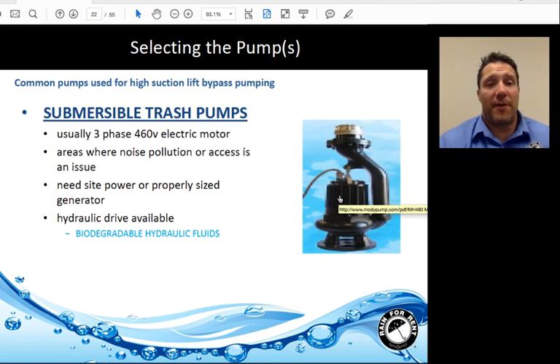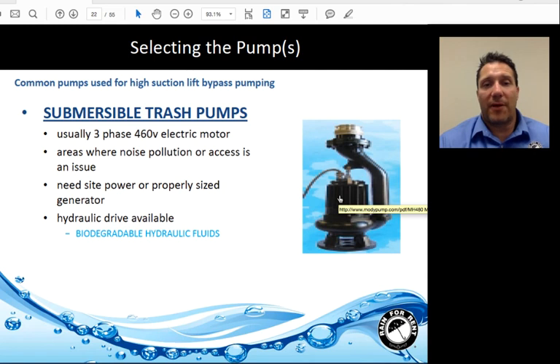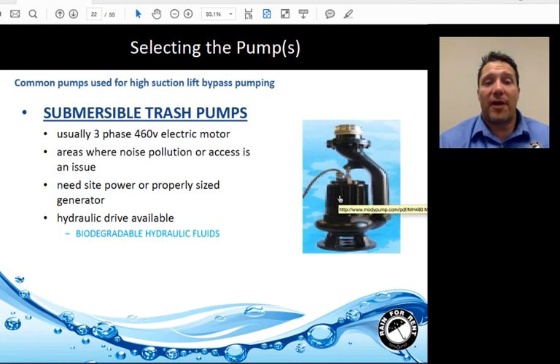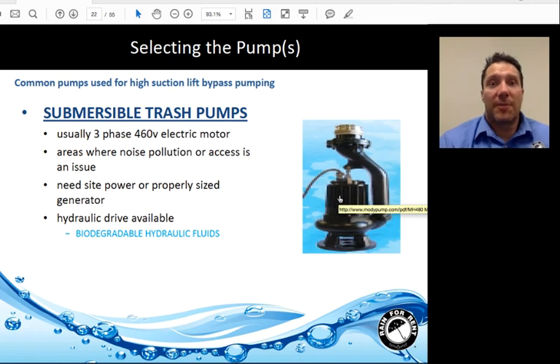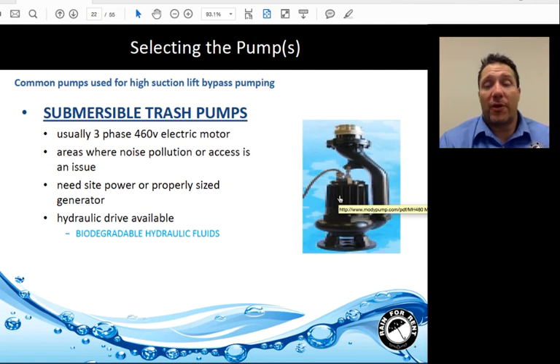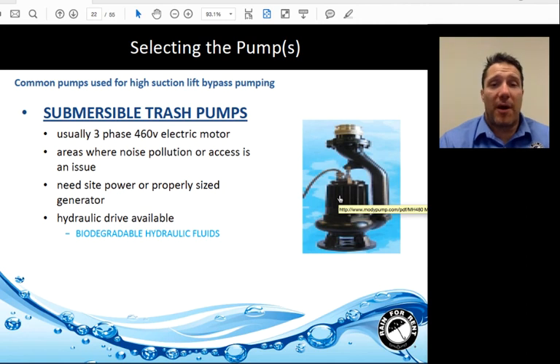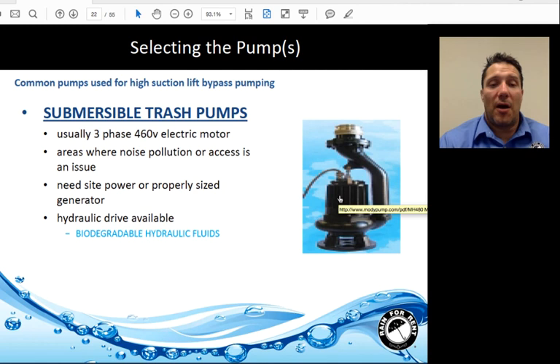A submersible trash pump is typically used when there's high suction lift, or space and access constraints. They are usually three-phase, 460-volt electric motors. When using a submersible electric pump, consider where power will come from — a generator or permanent power source — and what backup power is needed. Submersible pumps are also available in hydraulic drive units, which can be equipped with biodegradable hydraulic fluids.